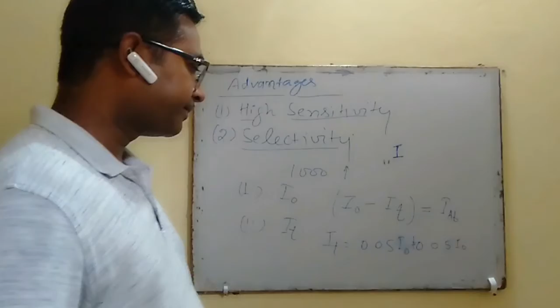In UV visible spectrophotometry, the difference between the intensity of incident radiation and intensity of transmitted radiation, that is in the range of I_T equal to 0.05 I naught to 0.5 I naught. So if the difference in the intensity of incident radiation and intensity of transmitted radiation is very minute, it approaches the noise level and the detector does not respond to the signal. But in case of spectrofluorimetry, a single beam of radiation passes to the detector, whose intensity is measured, and therefore its sensitivity is very high.